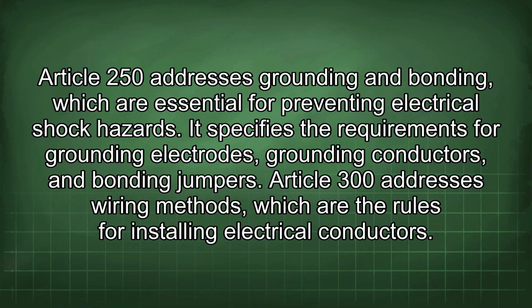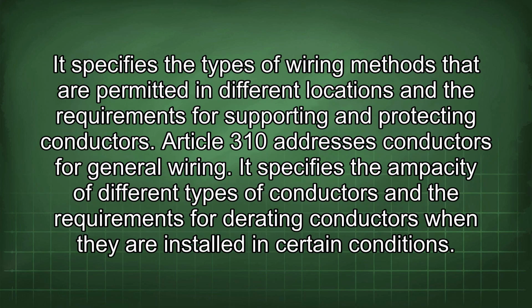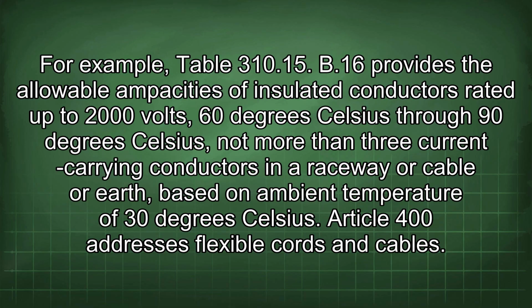Article 300 addresses wiring methods, which are the rules for installing electrical conductors. It specifies the types of wiring methods that are permitted in different locations and the requirements for supporting and protecting conductors. Article 310 addresses conductors for general wiring. It specifies the ampacity of different types of conductors and the requirements for derating conductors when they are installed in certain conditions. For example, Table 310.15.